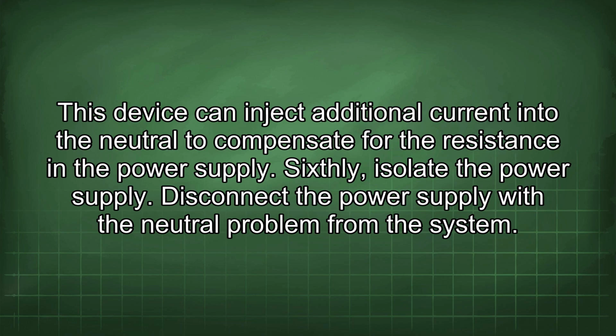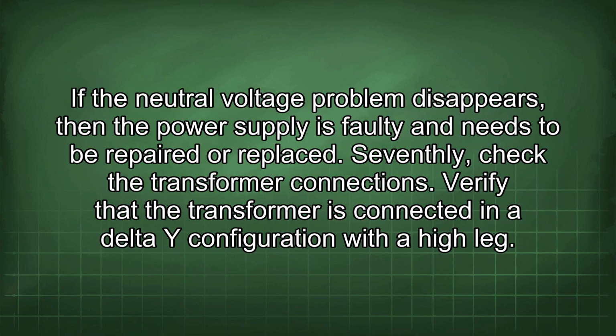Sixthly, isolate the power supply. Disconnect the power supply with the neutral problem from the system. If the neutral voltage problem disappears, then the power supply is faulty and needs to be repaired or replaced.